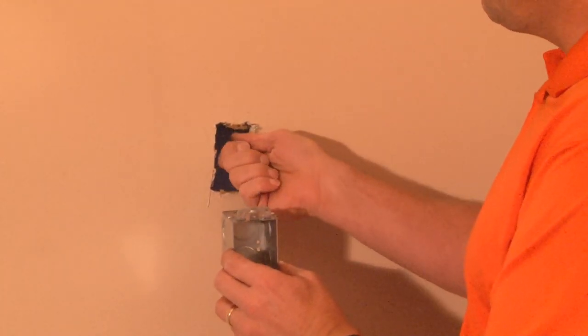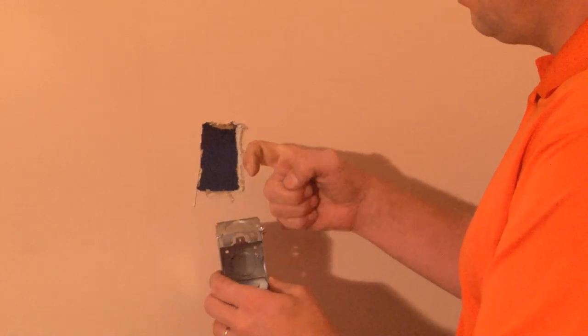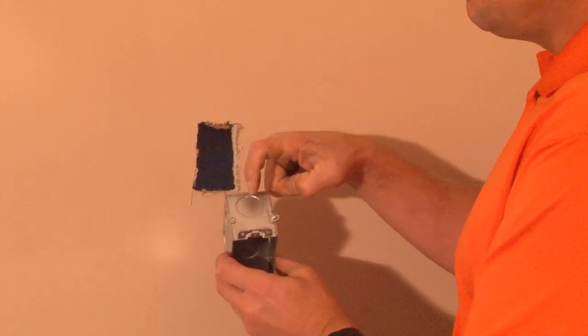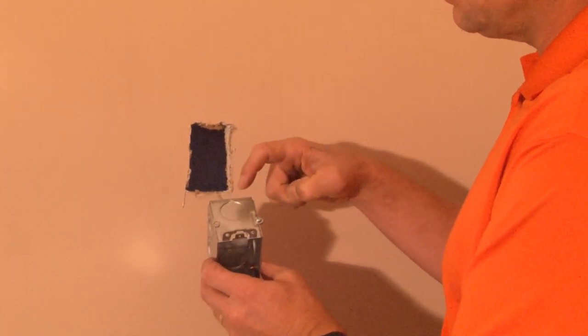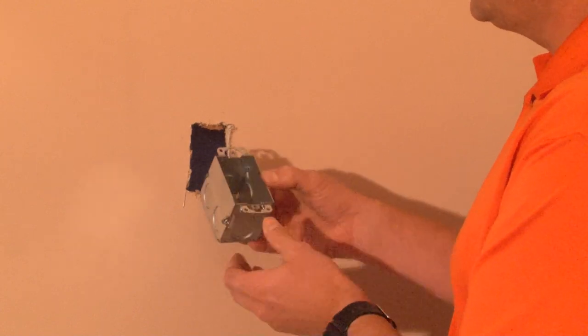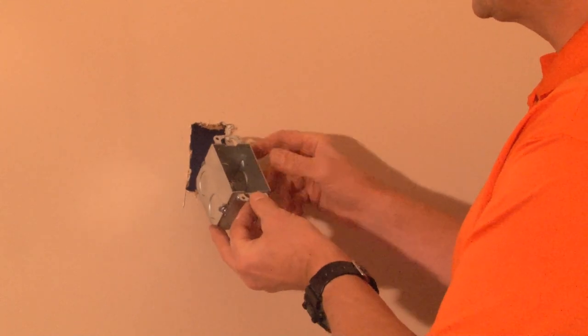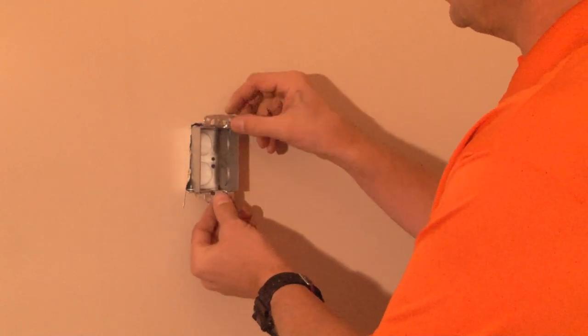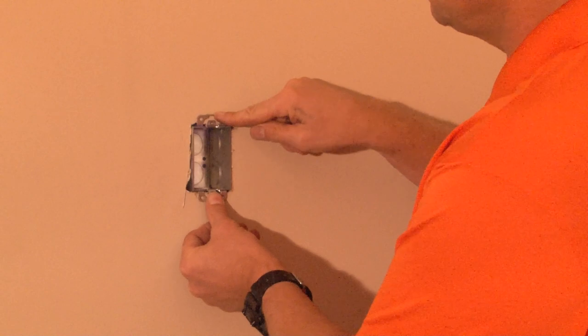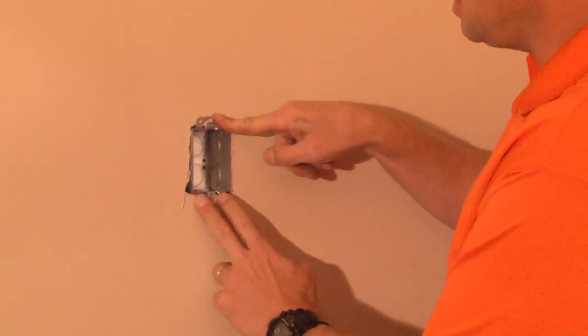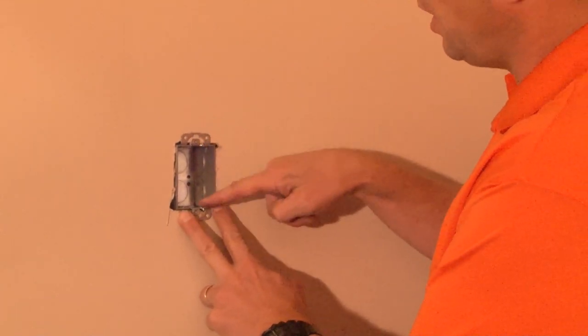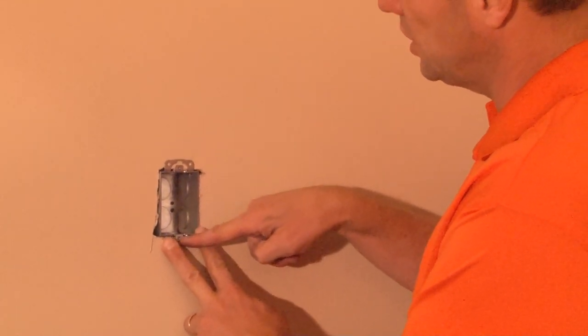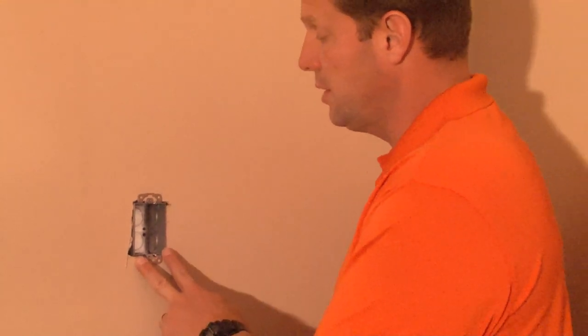After you pull flexible metal conduit through the wall and remove one of the 3/4 inch conduit connectors and install it, you simply slide the box inside the opening and the devices can now be installed and wired up using the 6-32 threaded holes.